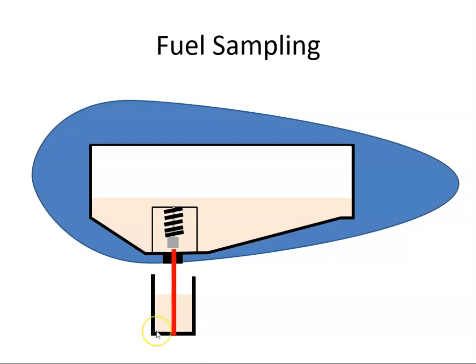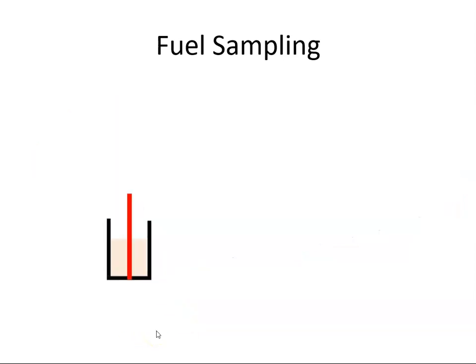Once the sample is taken, the sample jar is removed and a visual inspection is performed. Looking through the jar, if there is any free water, you would see it at the bottom of the sample jar. You're looking for little droplets or cloudy portions in the fuel, which would indicate entrained water.